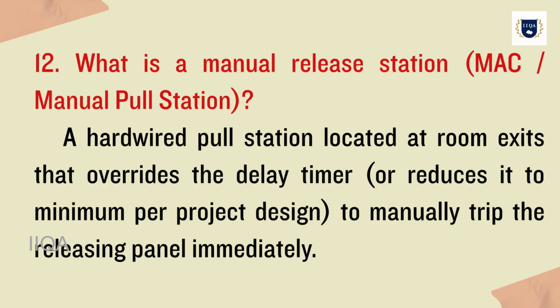12. What is a manual release station, MAC, manual pull station? A hardwired pull station located at room exits that overrides the delay timer or reduces it to the minimum per project design, to manually trip the releasing panel immediately.